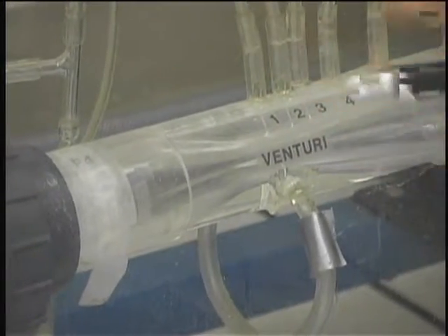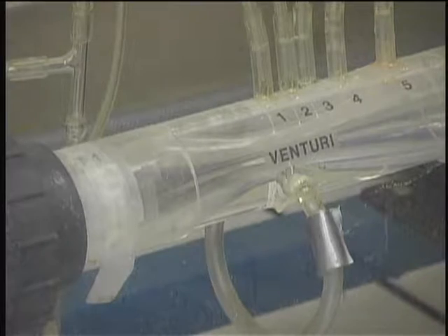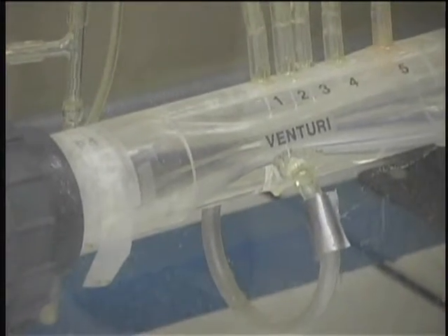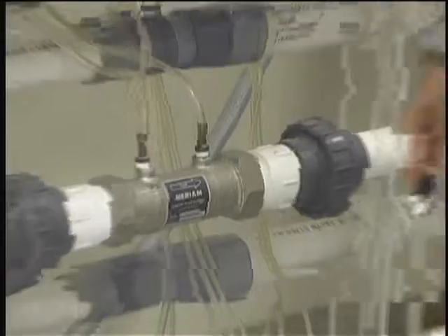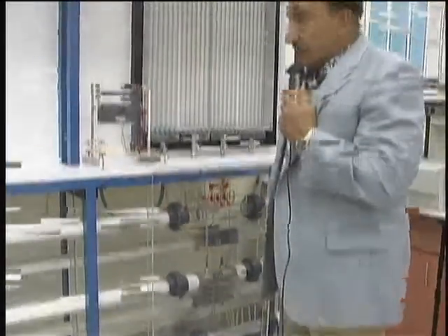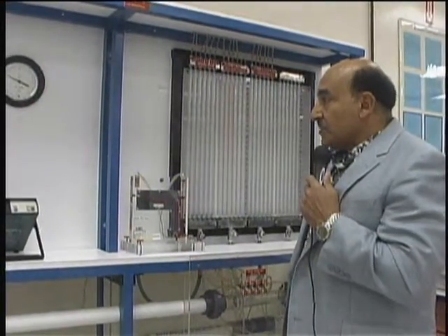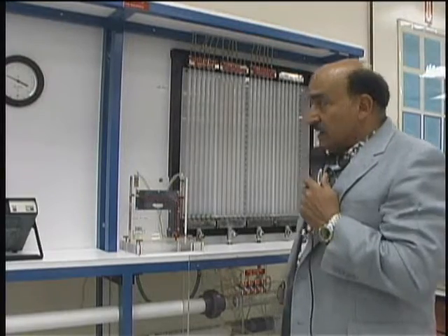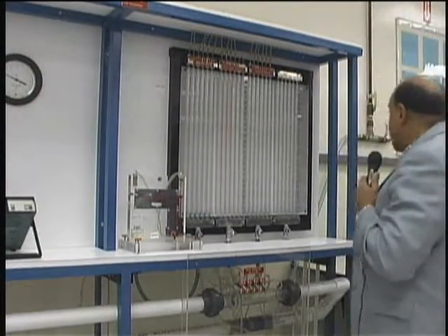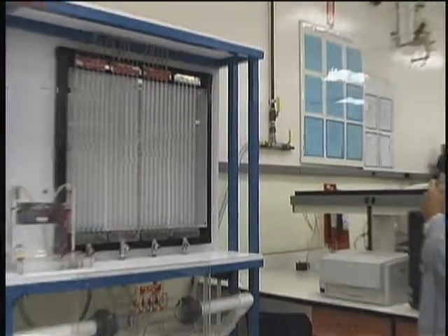And then we're going to use this as the reference condition for the discharge coefficient as we discussed in our lecture. So now let's see how it works. Basically, if the air pressure is not introduced in the system, you have to turn this handle to allow system pressure to come in, but it's already turned to flow because it's pointing horizontal. It means that I have flow already. And then I check the pressure here, 15 psi.